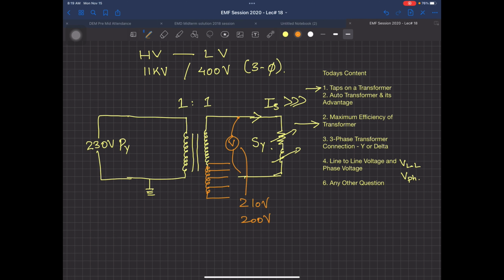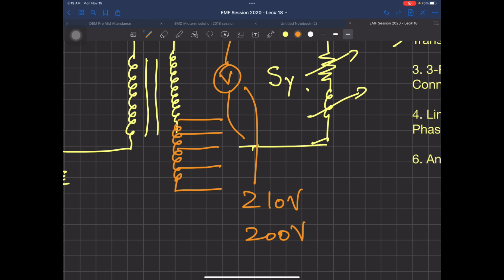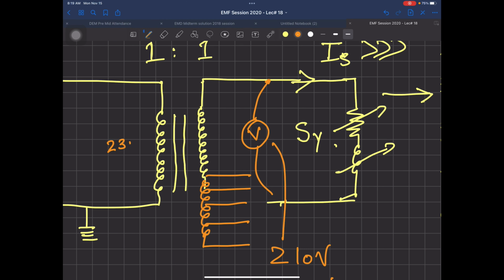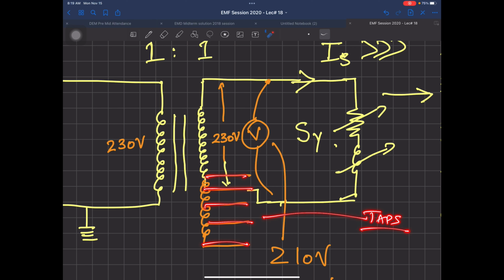Now what are these tappings? These tappings are additional number of turns. Suppose you have 230 volt applied with a 1-to-1 ratio, you are going to get 230 volt from here till here. But now, because of the voltage drop, the voltage is 210 volts. So you will increase your turns: instead of taking the voltage up till this point, you will connect this one with this one. Now your voltage will still be 230, because the voltage drop is compensated. So these taps, 1, 2, 3, 4, 5, are called the taps on a transformer, so that you can control your voltage regulation, or the regulation of your voltage at the load.